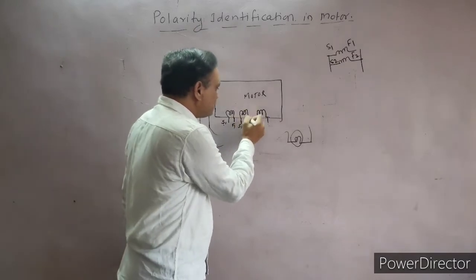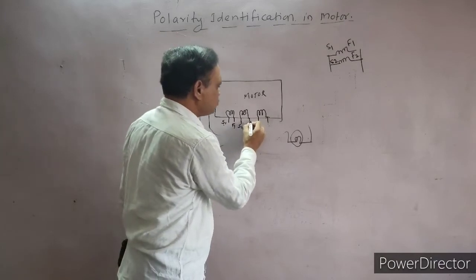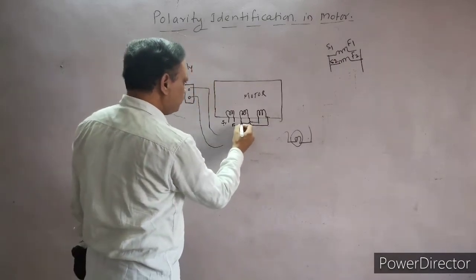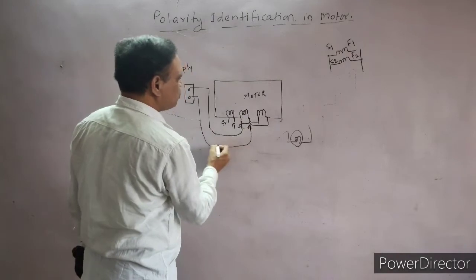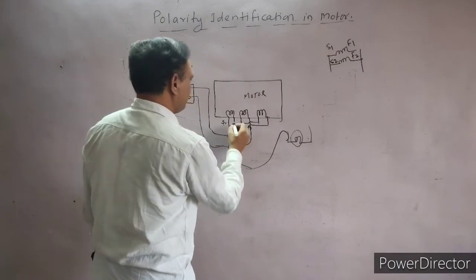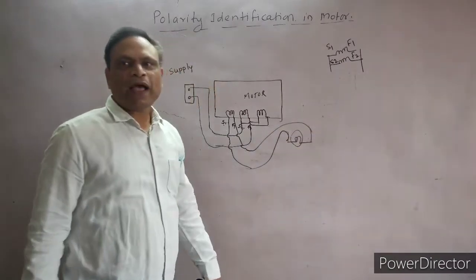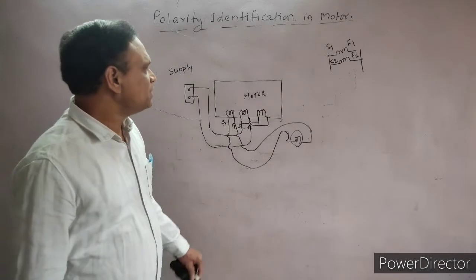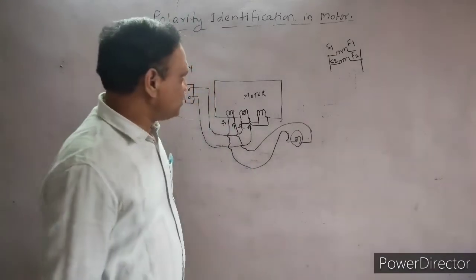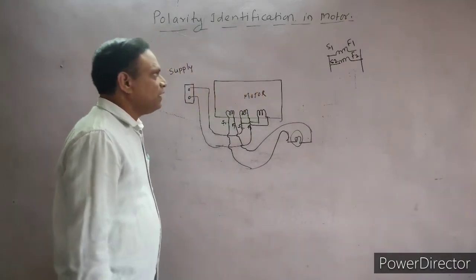We keep this terminal fixed and connect the lamp across the third coil pair. We connect the power supply to these two terminals and connect the lamp across the third coil. Now say the lamp has not glowed. That means we have connected in series opposition — S1 is connected to F2 and F1 is connected to S2 — which is a reverse connection.